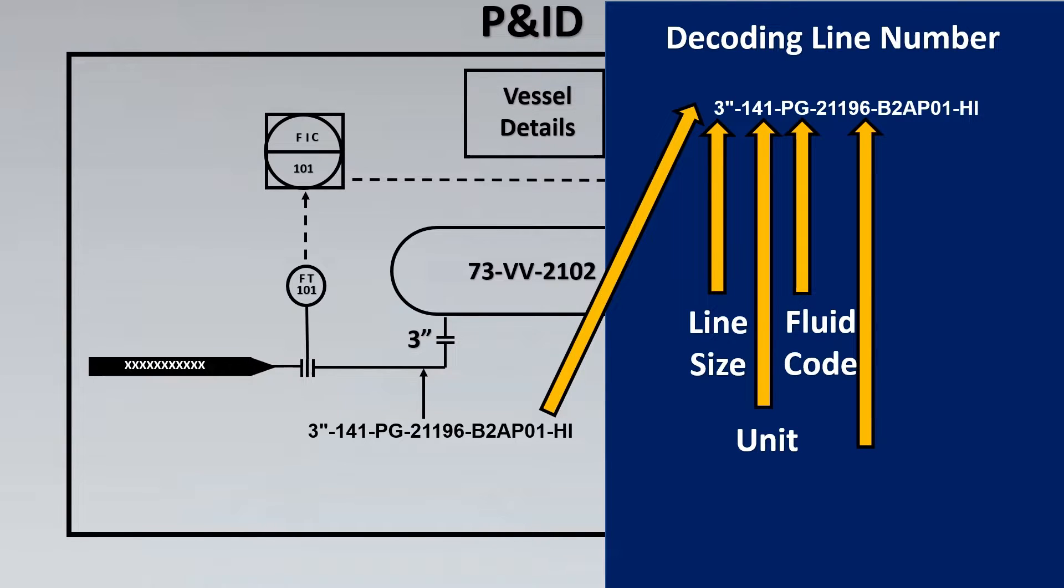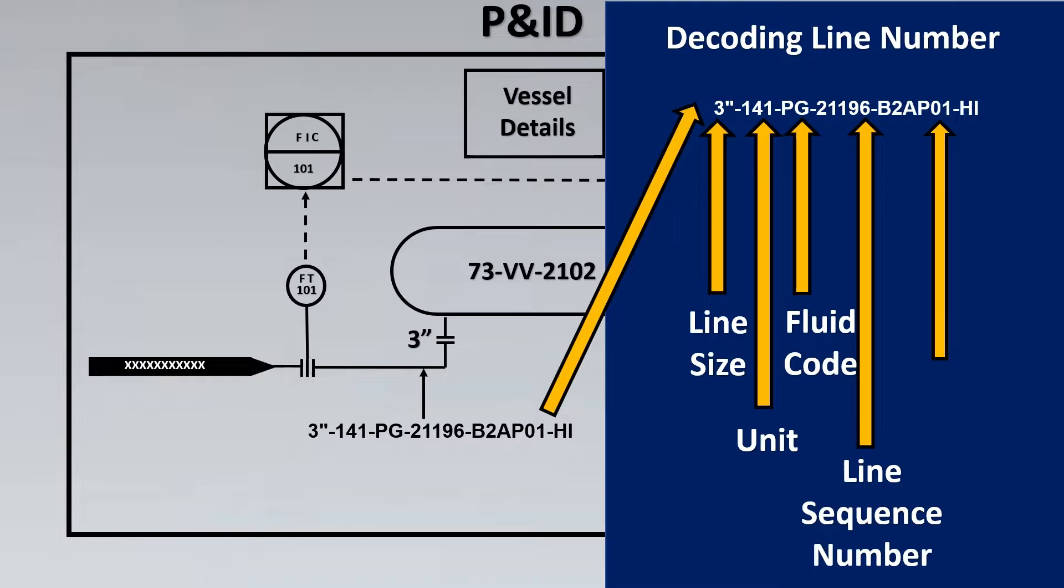This is like the tag number, a sequence number to the line because lines might be 10, 20, 50,000 lines in a plant. So you can understand very easily that as per this unique sequence you can identify the lines. Finally this is one of the extremely important thing which is called pipe specifications, and I would call in simple words DNA of the pipe. With this pipe specification you can search in the document called pipe specifications, and with this number you will find out what is the rating of the pipe, material of the pipe, corrosion allowance, what type of gasket you can use, what is the trim material of the valve, every single thing related to it. This is extremely important.